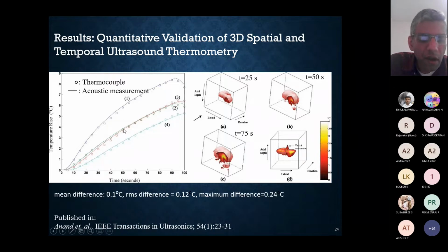We were able to quantify objectively what the difference is between the thermocouple profile and the actual measurements using ultrasound, and these are very accurate — on the order of 0.1 degrees Celsius, with a maximum difference of 0.24 degrees. So through this project, we were able to demonstrate that we can effectively do 3D temperature estimation with high accuracy, on the order of less than 1 degree, in many cases 0.1 degree, and therefore we can use this as an effective temperature estimation modality.